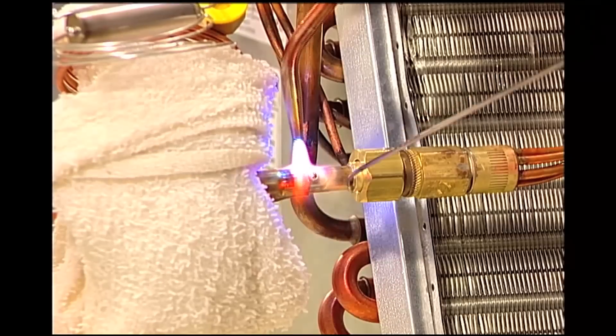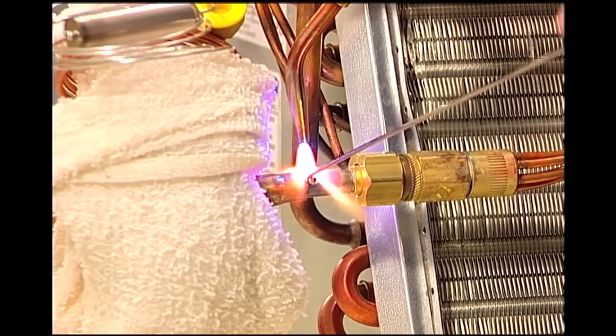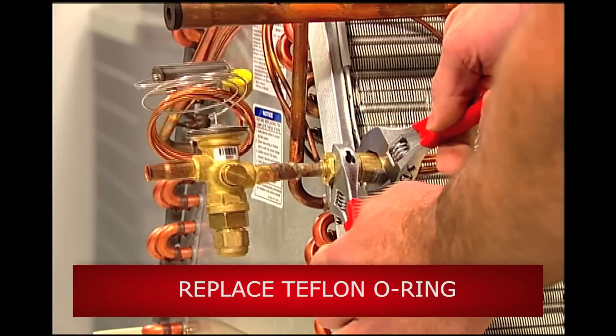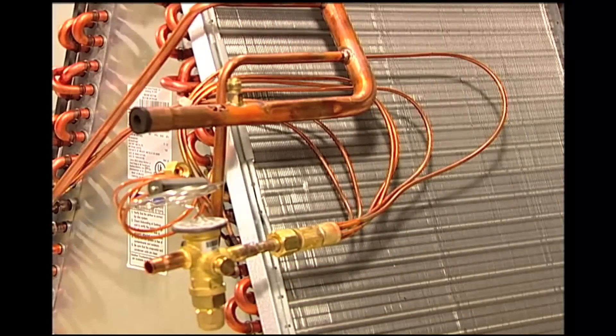keep the towel in place while you sweat the connector to the existing 3/8-inch liquid line pipe. Remove the towel, replace the Teflon O-ring if equipped, and tighten the outlet coupling.